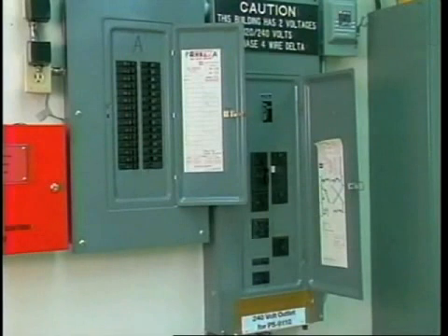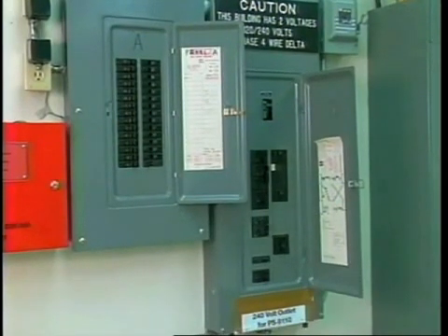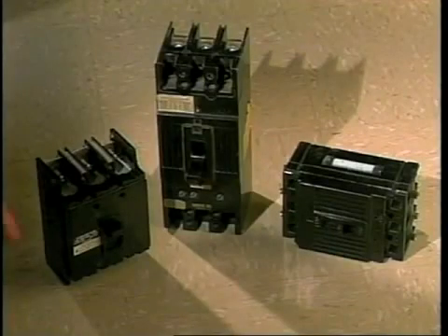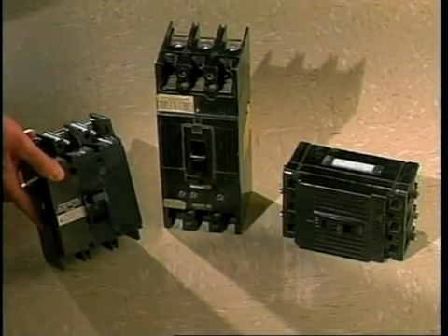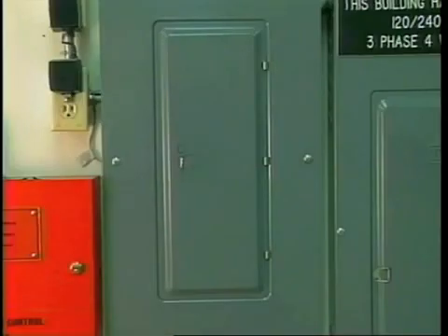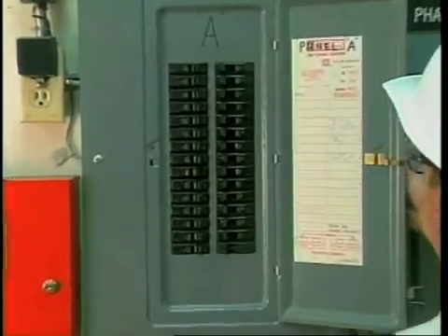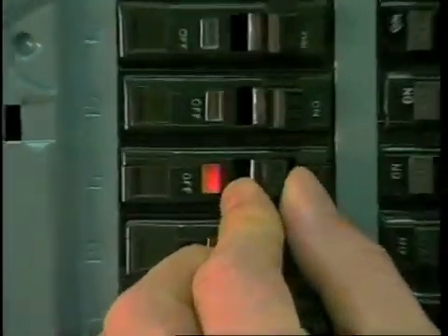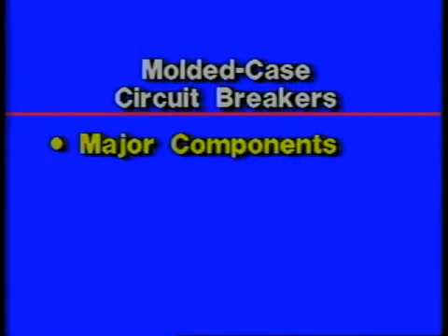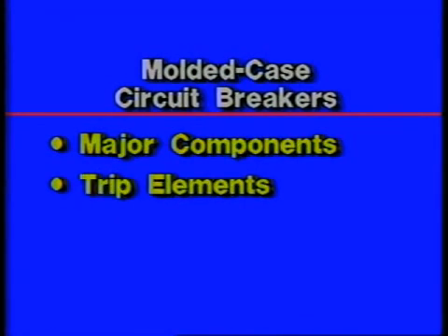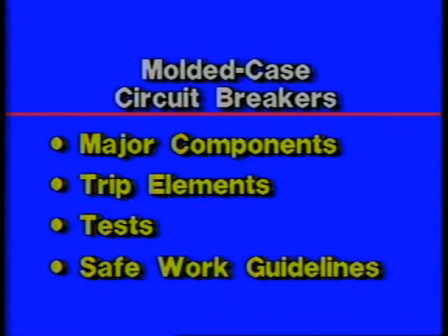Molded case circuit breakers are commonly used devices for low voltage circuit protection. They're available in a wide range of sizes and ratings and have many applications. Molded case circuit breakers are normally used where a resettable circuit interrupting device is needed. In this program, we're going to look at the major components of molded case circuit breakers. Identify the 4 trip elements used in molded case circuit breakers.